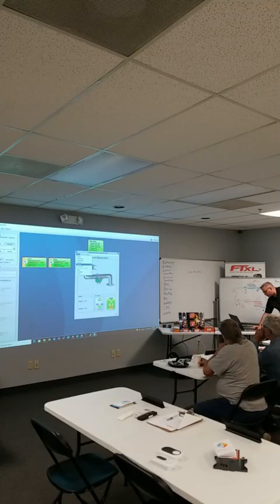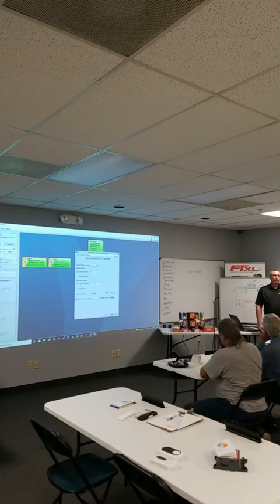So a couple other things on the zone, then I'm gonna move on to the rooftop controller. We can set this up like it's a duct heater. It's got an interlock here, so if it sees 122 degrees coming from the rooftop, like W1's calling, it's like boom, no, don't run the duct heater for the zone. I'm not trying to reheat 122 degree air, I already got 122.